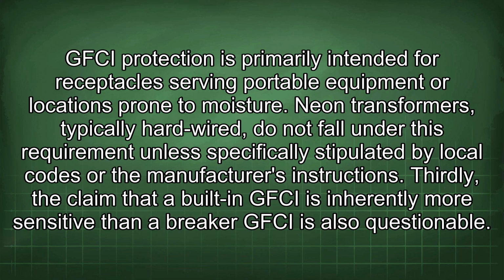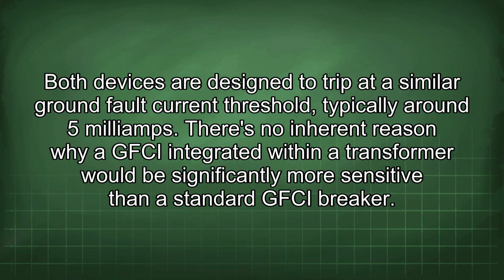Thirdly, the claim that a built-in GFCI is inherently more sensitive than a breaker GFCI is also questionable. Both devices are designed to trip at a similar ground fault current threshold, typically around 5 mA. There's no inherent reason why a GFCI integrated within a transformer would be significantly more sensitive than a standard GFCI breaker.